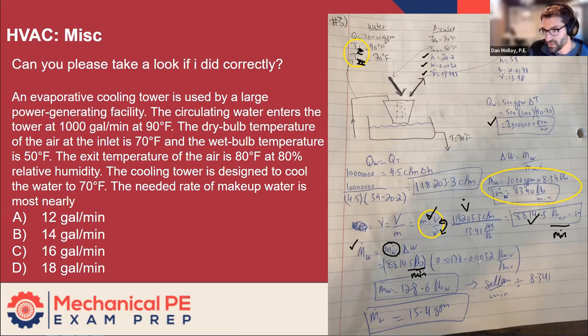Yeah. And then just finishing up, you did mass flow rate times the change in humidity ratio, which is correct. And you got the right mass flow rate, which is pounds. This should still be pounds per minute at this point. And then you change the gallons and you get the right answer. So we're good there. The only other thing I noticed was you took the time to find the mass flow rate of water, which is the mass flow rate of water around the condenser water system. So this is the water side. So I guess you calculated it, but then you decided not to use it for anything. You just sort of found it and then put it to the side.